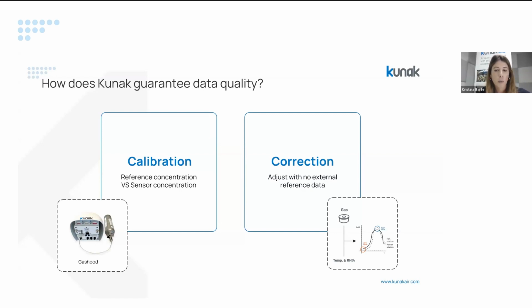As I said previously, the World Meteorological Organization insists that in order to ensure the proper performance of the devices and the quality of the data, it is necessary to perform a correct installation and maintenance of the stations. At Kunak we wanted to avoid additional maintenance costs, and that's why we released the gas hood. The gas hood tool lets you perform a proper calibration using a gas cylinder and a gas hood connected to the station, similar to the calibration protocol for reference instruments.